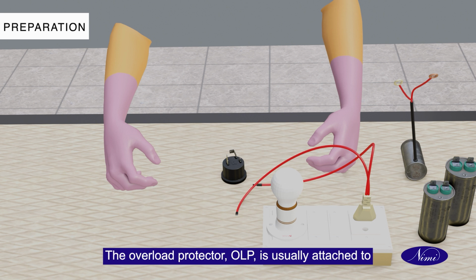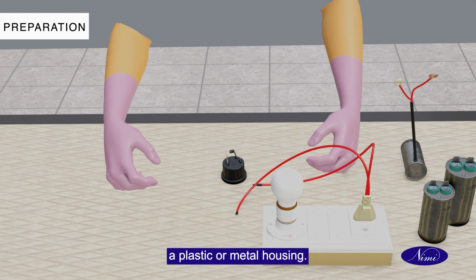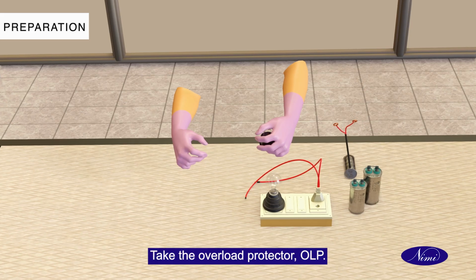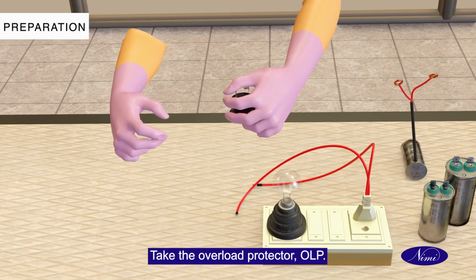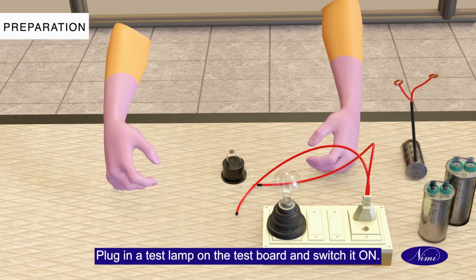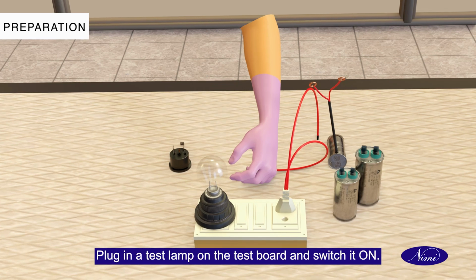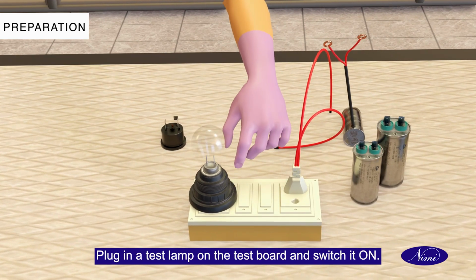The overload protector OLP is usually attached to the compressor and might be covered by a plastic or metal housing. Take the overload protector OLP. Plug in a test lamp on the test board and switch it on.